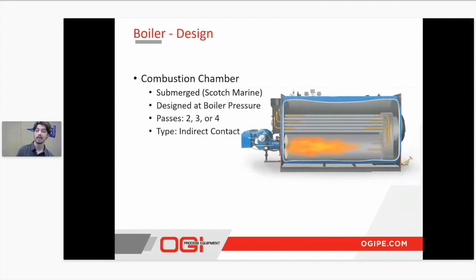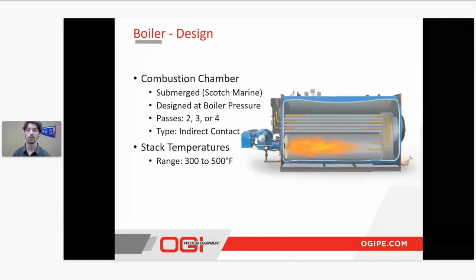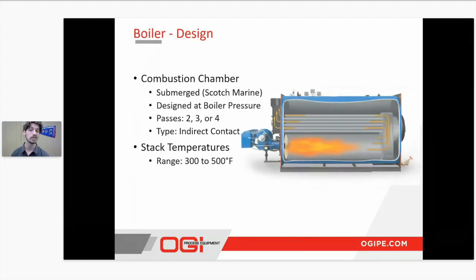As far as the design of the boiler goes, your combustion chamber is going to be typically submerged, with multiple passes, typically 2, 3, or 4, whereas on the QuikWater, we just have a single pass in our combustion chamber. And as well, a boiler is going to be an indirect contact heating solution. Stack temperatures on a boiler are typically going to range from about 300 to 500 degrees Fahrenheit, and that also depends on what you're running with your process, how hot you need your water or your steam.